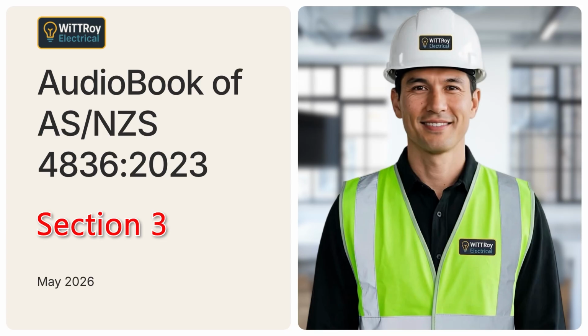After that, the electrical equipment and conductors must be isolated from all energy sources. Then the isolation must be secured, so it cannot be operated by mistake. If stored energy is present, it must be discharged where necessary. For example, capacitors may hold energy even after the supply has been disconnected. After that, the de-energized condition must be proven by testing. The limits of the safe area of work must also be identified. Warning notices must be displayed where needed to reduce the risk of injury or death.